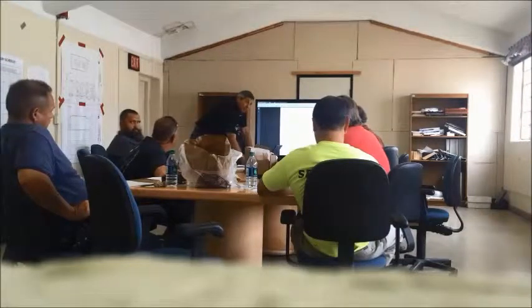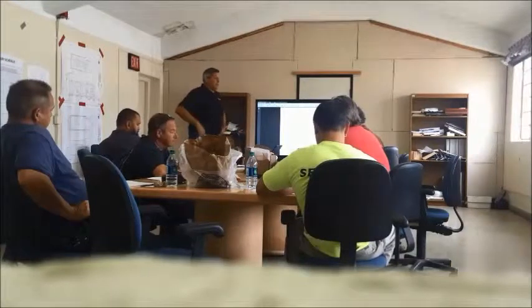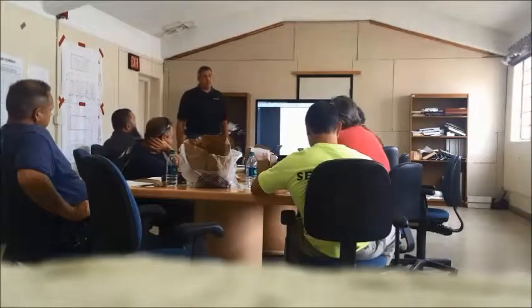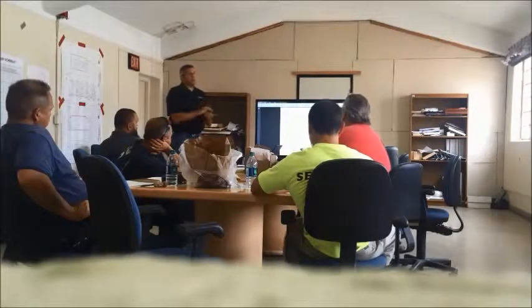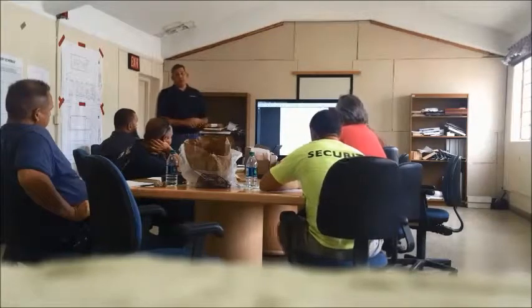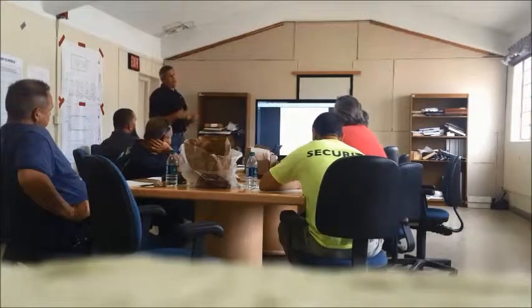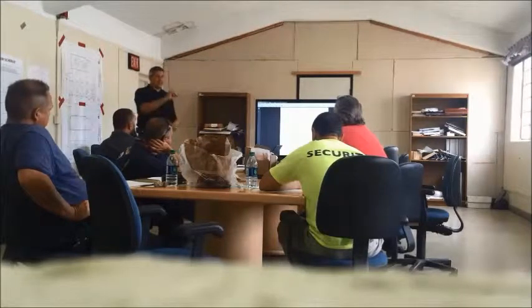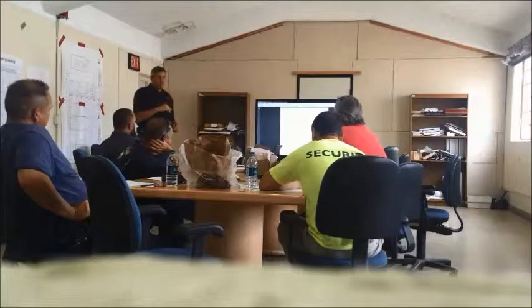And so the monitor gets that alarm signal from that processor. Yeah, and then ultimately it goes into the Phoenix server, and then we broadcast that alarm condition over BACnet to the ALC system. The thing that is a little bit confusing for the commissioning stages is that a VAV box will tell you CFM. So when you have a set point and you show the graphics saying this is the CFM, you see the CFM changing, that's because it actually truly reads that value.